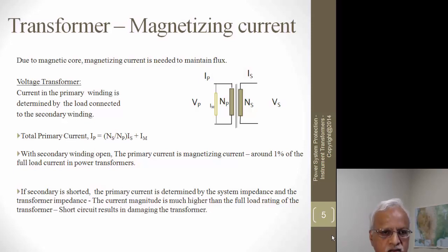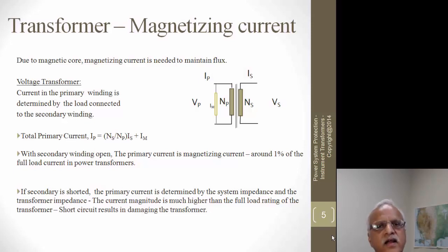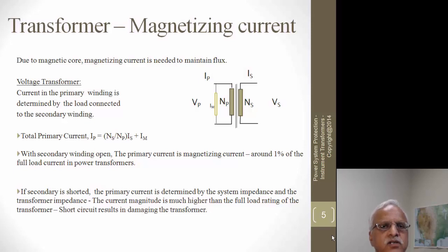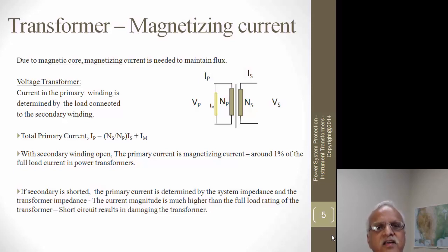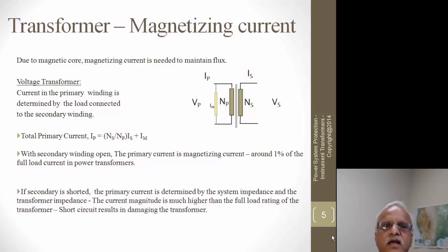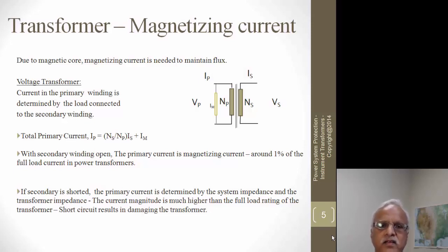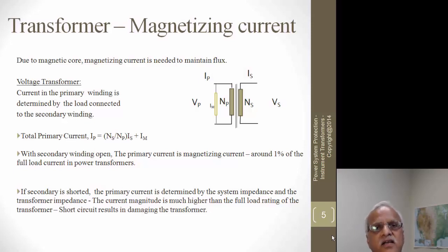The magnetizing current is only about one percent of the rated current of the transformer. In a voltage transformer, the secondary current is just the secondary voltage VS divided by the ohmic burden — the load connected on the secondary side, which we call 'burden' in instrument transformer vocabulary. That secondary current IS reflects back to the primary side, plus the magnetizing current.